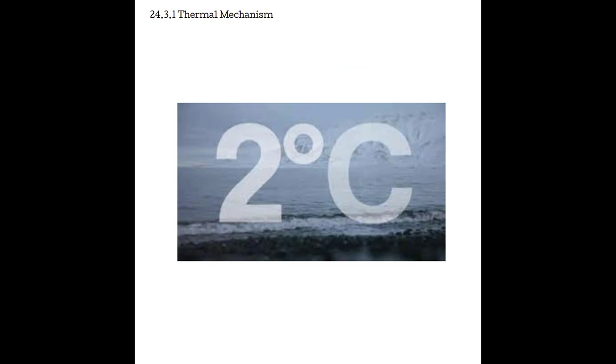Heating will increase when the intensity or the frequency increases. However, because of attenuation, high frequencies don't cause significant changes, especially deep into the body. What the studies have shown us is that temperature increases of more than 2 degrees Celsius have been shown to cause cellular impairment. So up to a 2 degrees Celsius increase in temperature has no known bio effects.